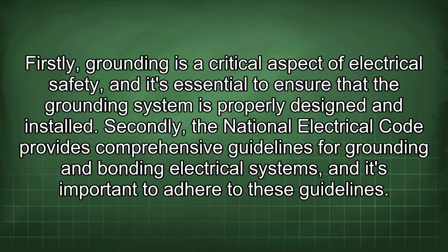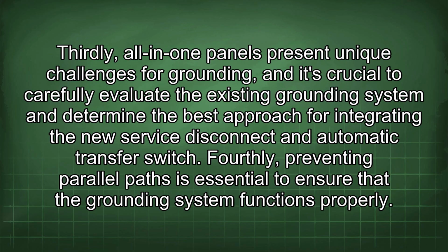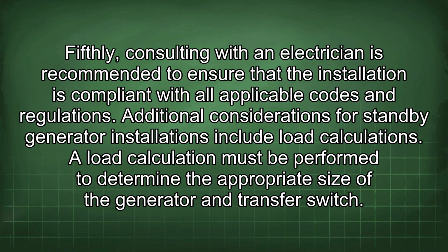Firstly, grounding is a critical aspect of electrical safety, and it's essential to ensure that the grounding system is properly designed and installed. Secondly, the National Electrical Code provides comprehensive guidelines for grounding and bonding electrical systems, and it's important to adhere to these guidelines. Thirdly, all-in-one panels present unique challenges for grounding, and it's crucial to carefully evaluate the existing grounding system and determine the best approach for integrating the new service disconnect and automatic transfer switch. Fourthly, preventing parallel paths is essential to ensure that the grounding system functions properly. Fifthly, consulting with an electrician is recommended to ensure that the installation is compliant with all applicable codes and regulations.